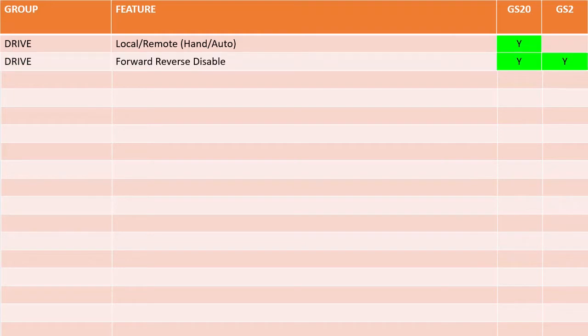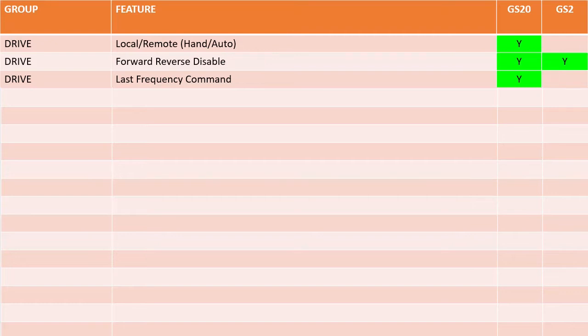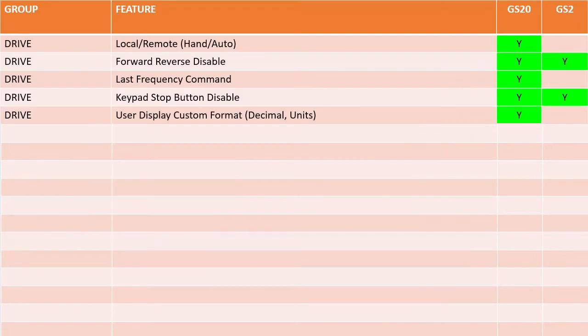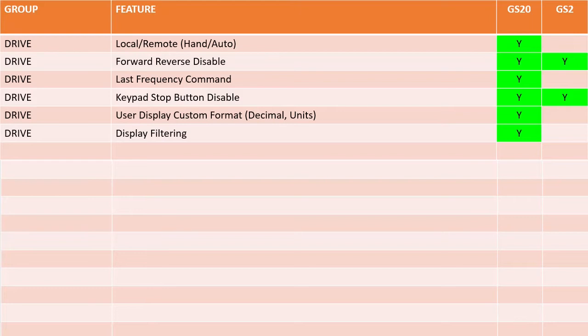Both drive families can disable forward or reverse for applications where you don't want the motor to run in one direction. On the GS20, if the keypad is the frequency source, you can retrieve the last frequency command in the event of a fault — that can be really handy when trying to debug faults. The GS2 can't do that. Both drives allow you to disable the stop button on the keypad. The GS20 also allows you to customize the display format of the user display, including decimal places and units displayed, and to filter the displayed values to make them easier to read.